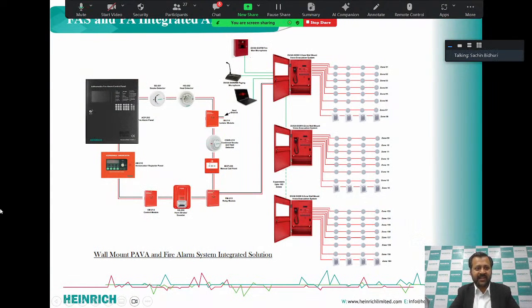So now, as you can see, this is the fire alarm panel and PA system integration. On the left, we have our fire alarm system, everything connected to it in a loop. Then with the help of a relay module, with NO/NC contacts, we have connected our PA control panel with the fire alarm system.